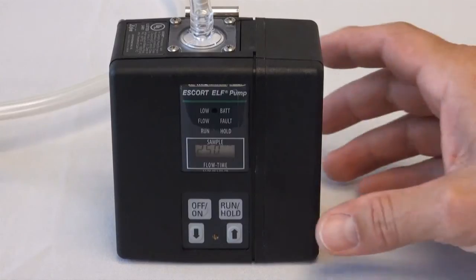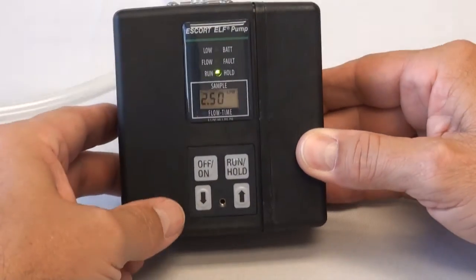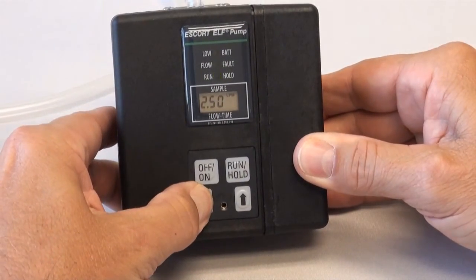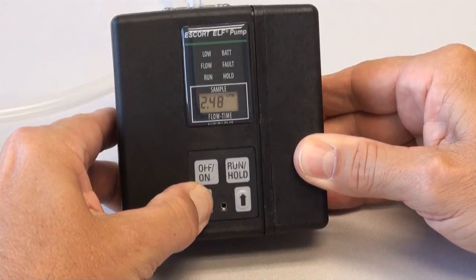Now, we will adjust the pump by using the flow rate control buttons. After the pump is set to match the calibrator, turn the pump off.